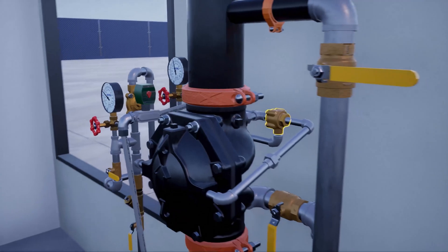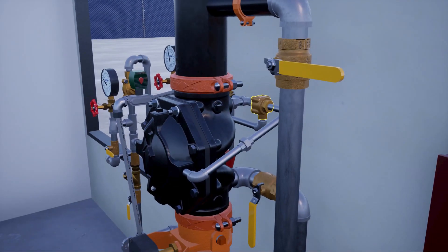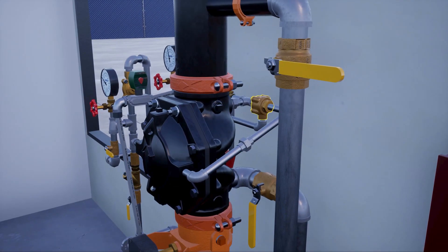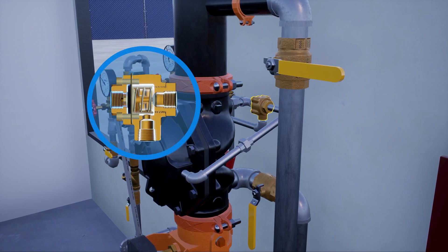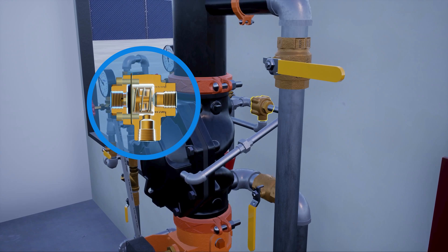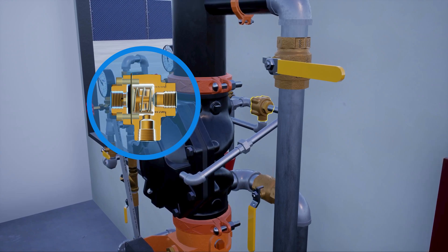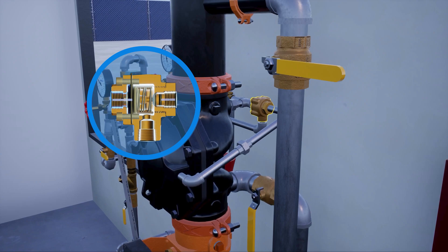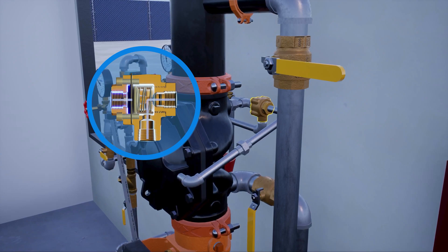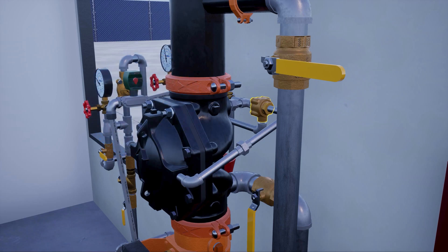Following the trim off of the prime chamber is the pressure operated relief valve. The pressure operated relief valve is a device that keeps a tripped valve in an open state. When activated, it will redirect prime water out to the drain cup, keeping the prime chamber from pressurizing until the water supply control valve is shut and the electric solenoid valve is reset.